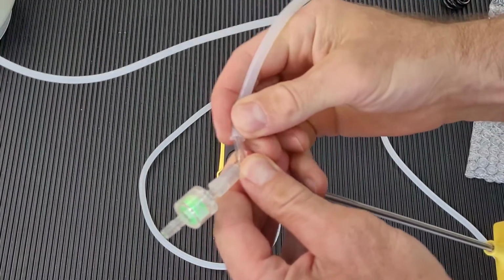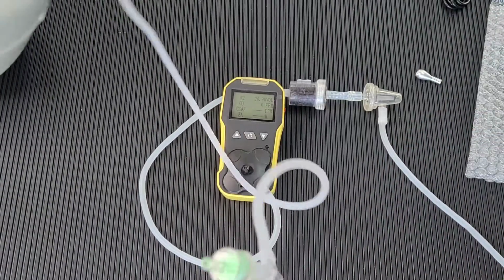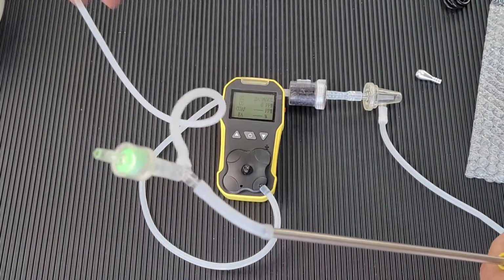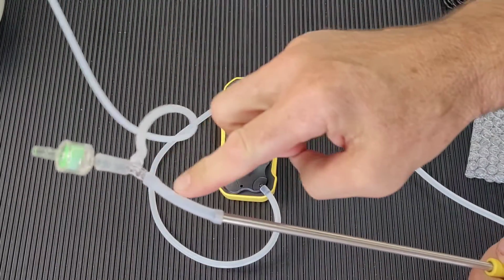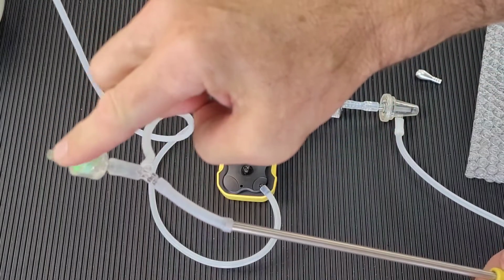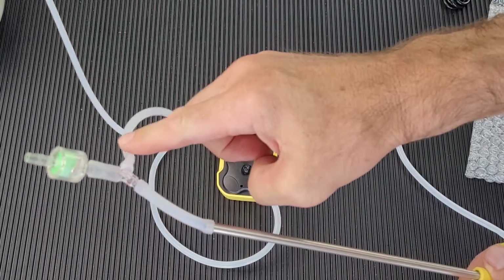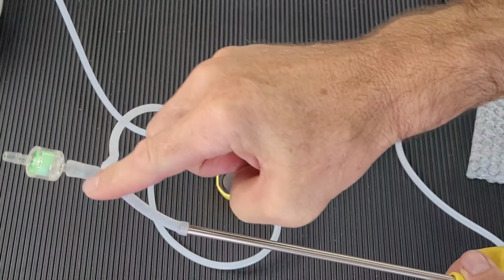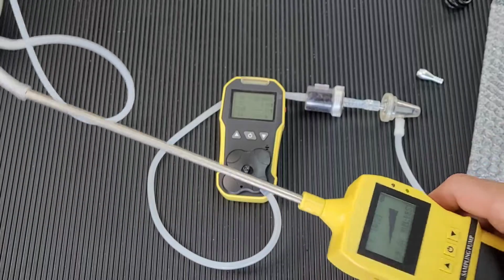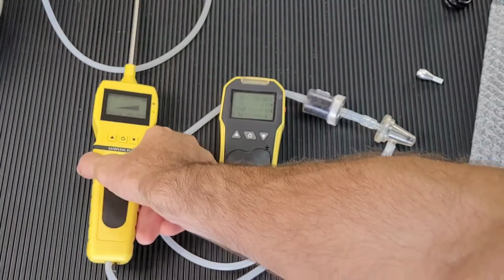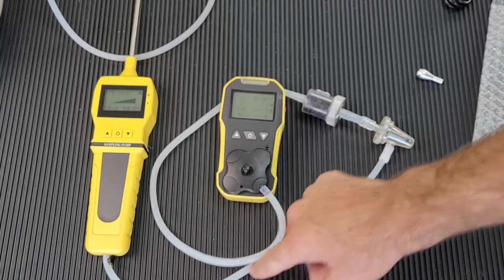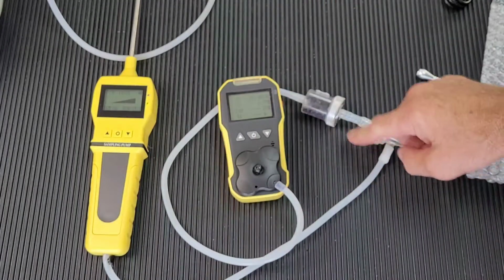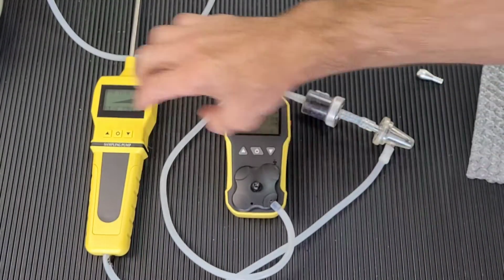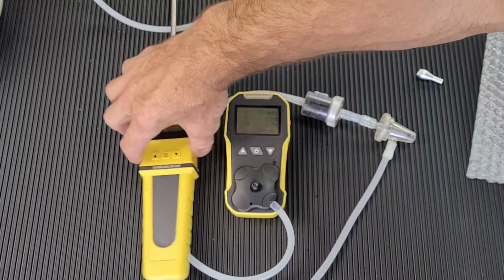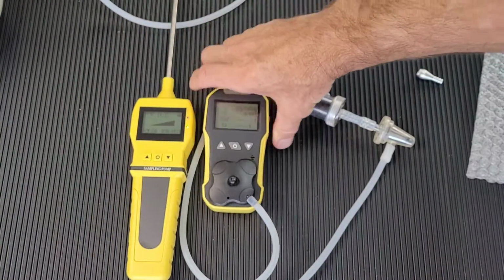Okay, folks. So again, you can see what's going on. We've got our gas bottle over here, our synthetic combustion gas coming in. Any excess air will go out. If there's not enough air, it's going to get drawn in, but I obviously want to put more air so it can escape, and whatever else is drawn and provided to the micro pump in this handheld unit. Okay, then it's expelled at the bottom. It goes through the water trap, the filters, and onto the analyzer. That's the way it works. Okay, so I'm going to turn on the gas and we're going to see where it takes us.